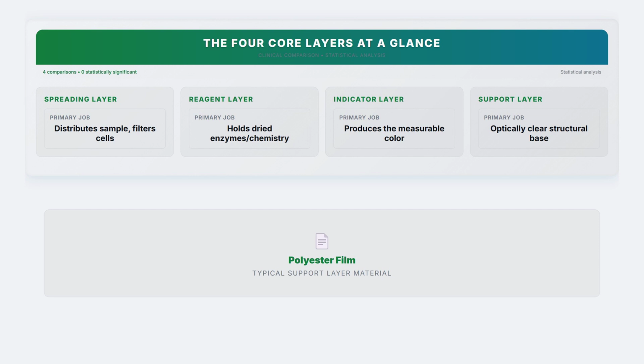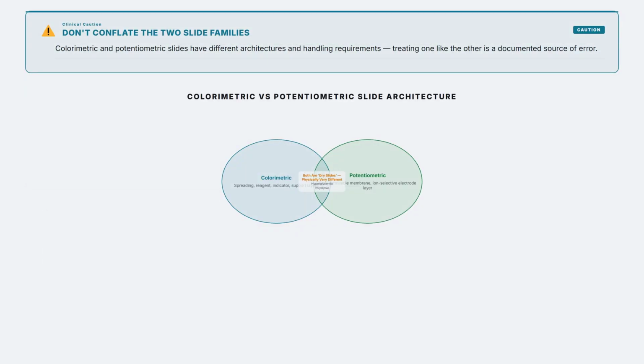Electrolyte slides swap this entire architecture for something different: a semi-permeable membrane and an ion-selective electrode layer, physically separating and detecting specific ions rather than generating color. Mixing up the two slide families' handling requirements, treating a potentiometric electrolyte slide like a colorimetric one, is a real, documented source of erroneous results in less experienced hands.